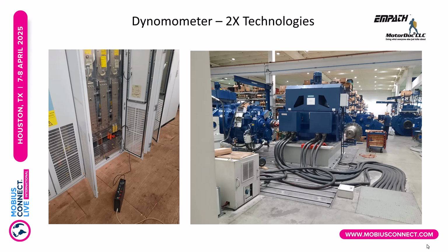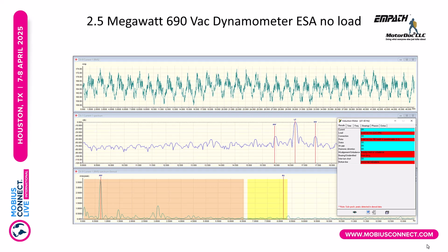Let's get to something a little more recent. In this case, we've got an electrical signature analyzer there on the left that is taking one phase of current because it was the safest thing to get to with the time and access we had. We actually had to leave the room when things ran, so we had it set up to trigger. That's the machine there on the right, and those are wind turbine generators. They were having problems with their dyno, so we went ahead and tested it.